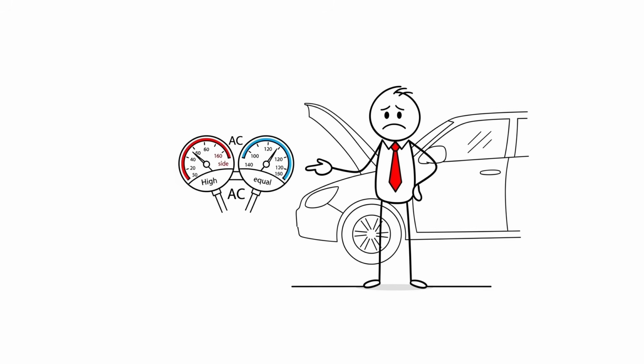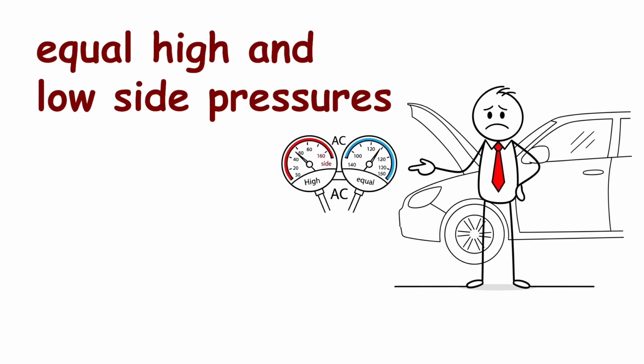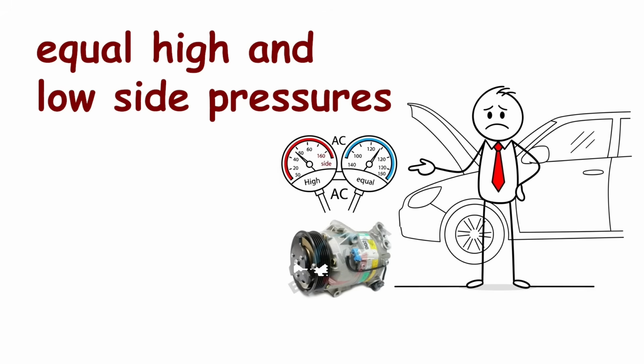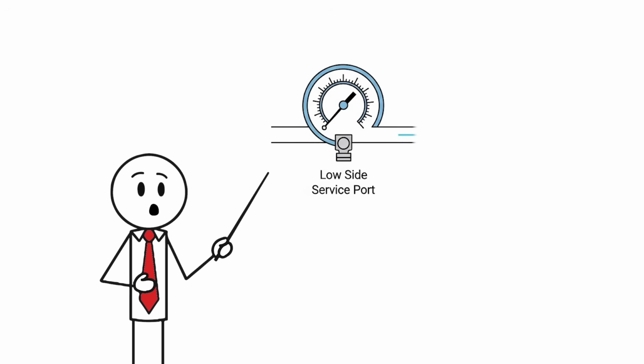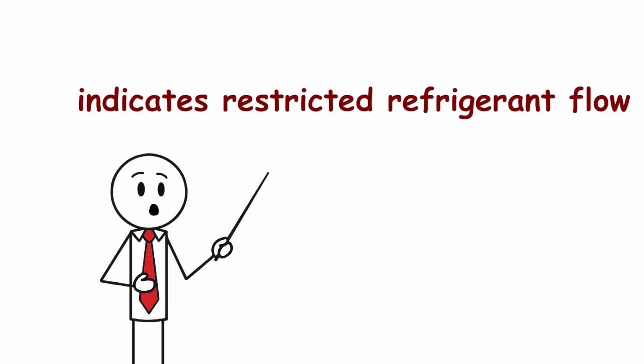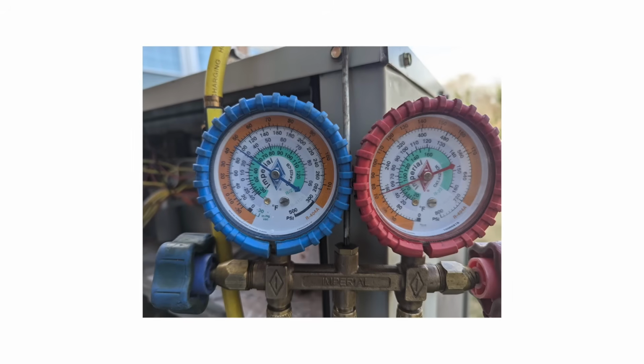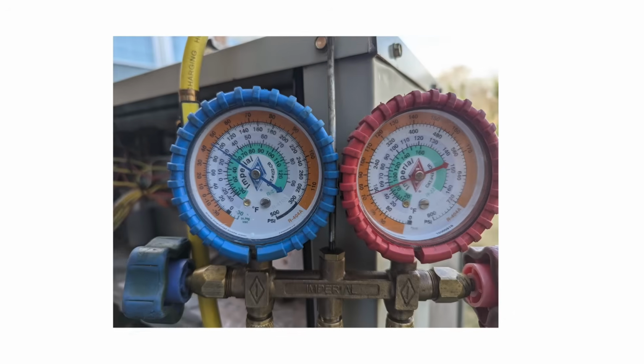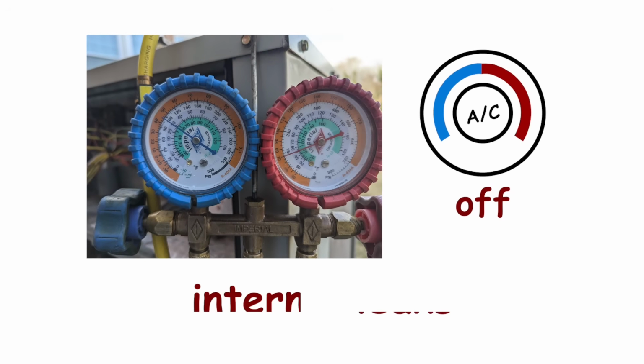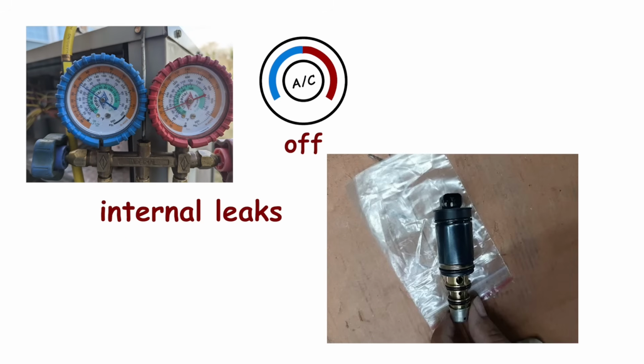Common diagnostic patterns include equal high and low side pressures, which indicates a non-functioning compressor. Very low side pressure with high side pressure indicates restricted refrigerant flow, typically from a clogged expansion valve. Refrigerant pressures that equalize quickly when the AC is turned off indicate internal leaks, usually compressor valve problems.